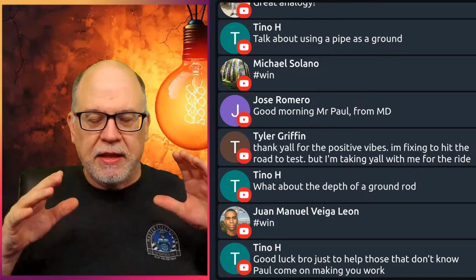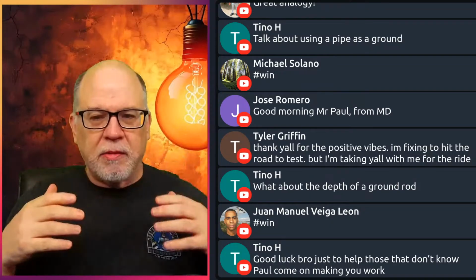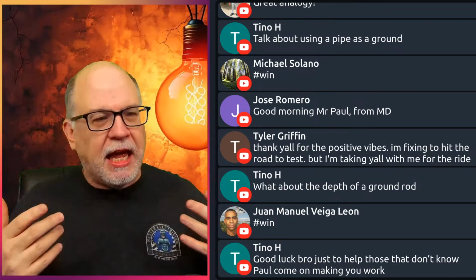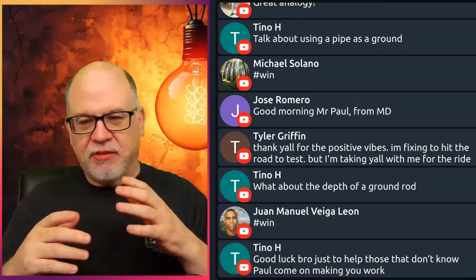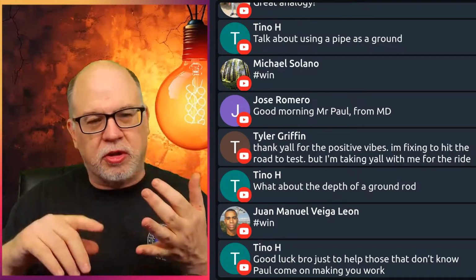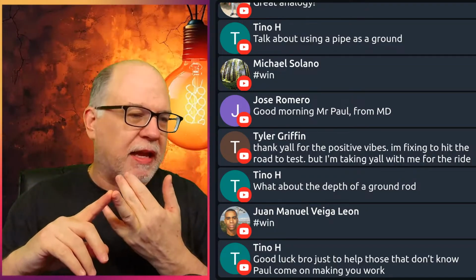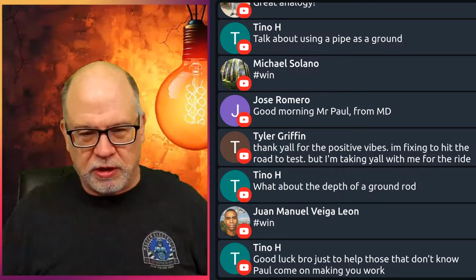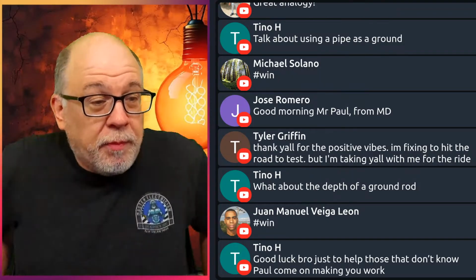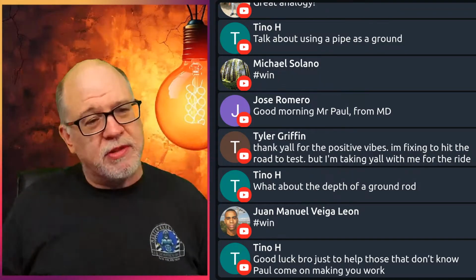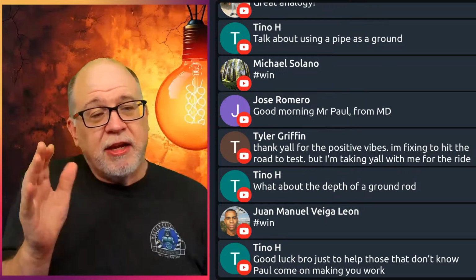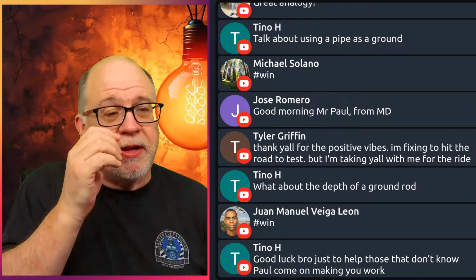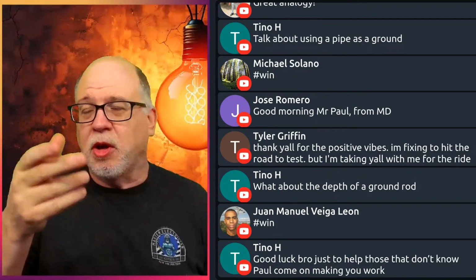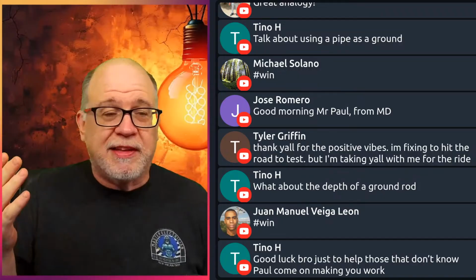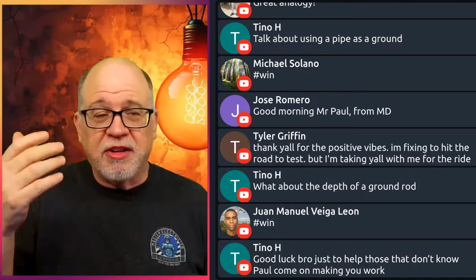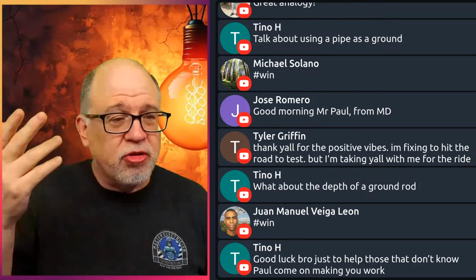But again, it's one of those things that people will get a lot of confusion over. That's not an equipment grounding conductor. That's not a bonding jumper, a supply side bonding jumper. That is a grounding electrode conductor. Now, here's a couple misconceptions that people have, and we'll probably cover these again later. Let's just take ground rods. So let's say I'm going from a panel down to ground rods. Y'all do this all the time. Y'all typically will probably use 250.66(A). You'll probably run a 6 copper. You'll run it down to ground rods, right?